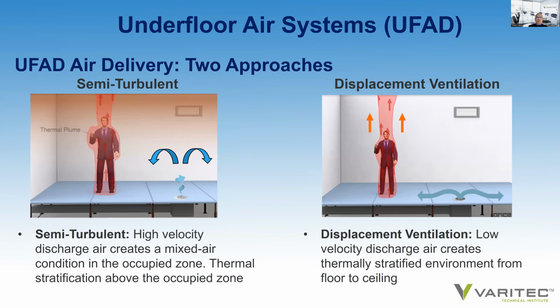There are two approaches to air delivery solutions using UFAD. The traditional early design was semi-turbulent, that is to say, high velocity discharge air emitted from the diffuser creates a mixed air condition in the occupied zone. Look at it as a micro mix zone. Thermal stratification occurs above the occupied zone. However, because the occupied zone is at space set point, which we anticipate to be 73 to 75 degrees, the thermal plume from a 98-degree occupant, hopefully 98 degrees, will still cause that air from the occupied zone to rise up with the plume into the upper levels of the room, carrying contaminants and pathogens with it.